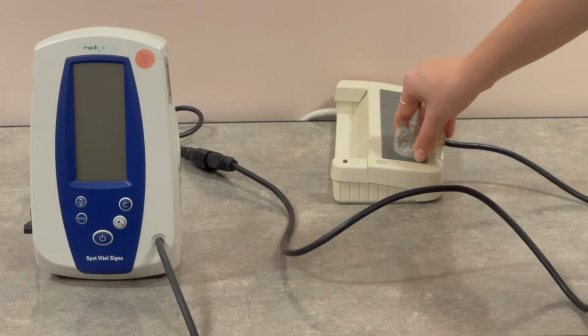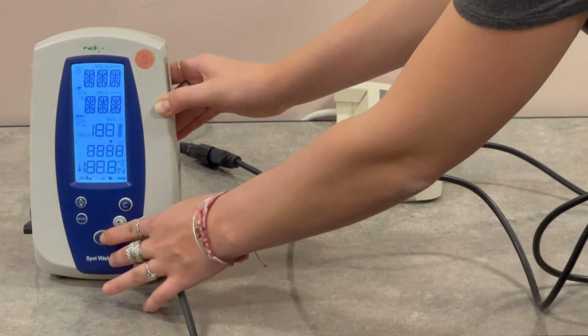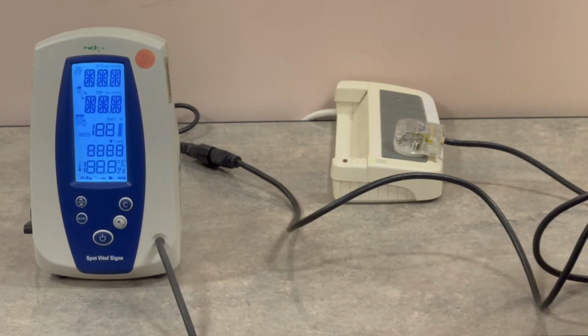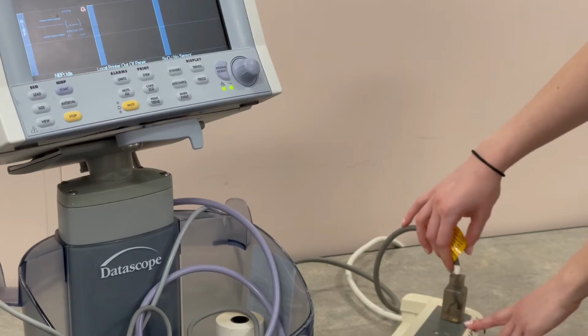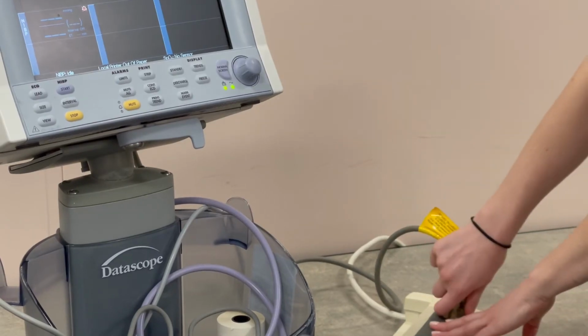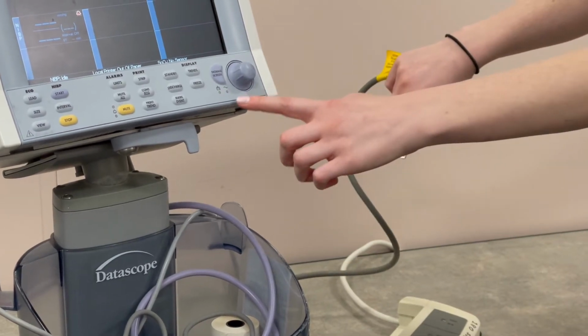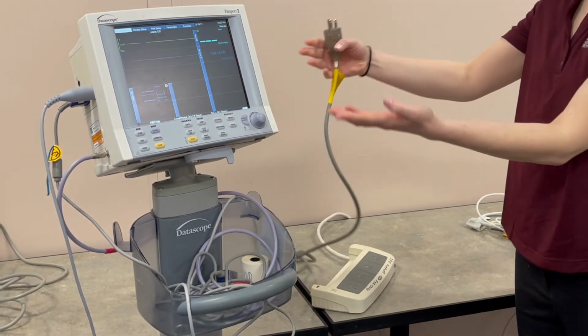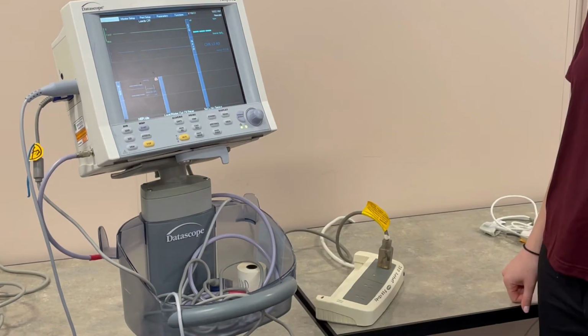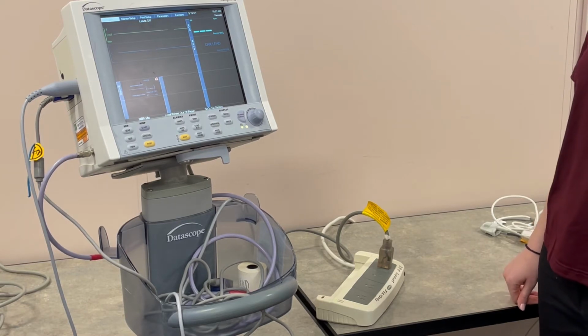Plug the patient monitor into a power outlet and turn it on. If the device has a self-test function, ensure that all tests are passed. For devices that have supplemental battery power operation, this function should also be checked when operated with this power source. The device will often come with the battery not charged and will need to be plugged in and charged to full capacity per the manufacturer's recommendations.